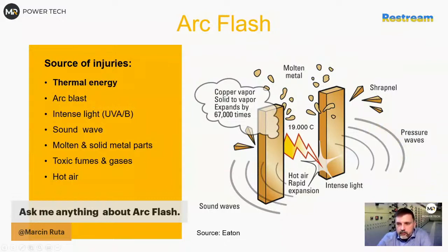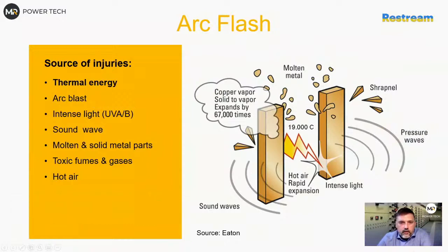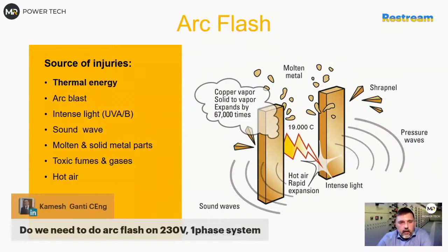Kamesh is asking if we need to do arc flash on a 230 volt, one phase system. The simple answer is yes, and it's not because I want to have it, but for the first thing, one phase systems are not really included in IEEE 1584, and we treat three phase to one phase more or less as one to one, as a rule of thumb.